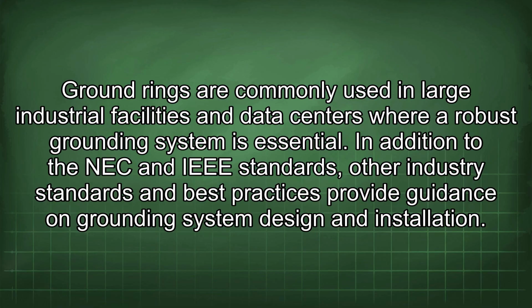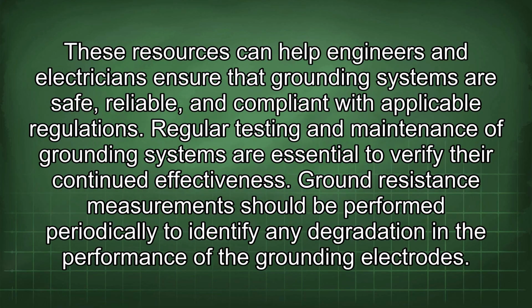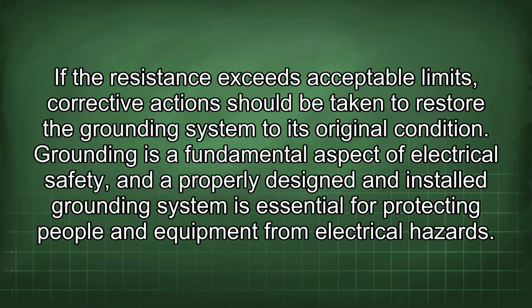In addition to the NEC and IEEE standards, other industry standards and best practices provide guidance on grounding system design and installation. These resources can help engineers and electricians ensure that grounding systems are safe, reliable, and compliant with applicable regulations. Regular testing and maintenance of grounding systems are essential to verify their continued effectiveness. Ground resistance measurement should be performed periodically to identify any degradation in the performance of the grounding electrodes. If the resistance exceeds acceptable limits, corrective action should be taken to restore the grounding system to its original condition.